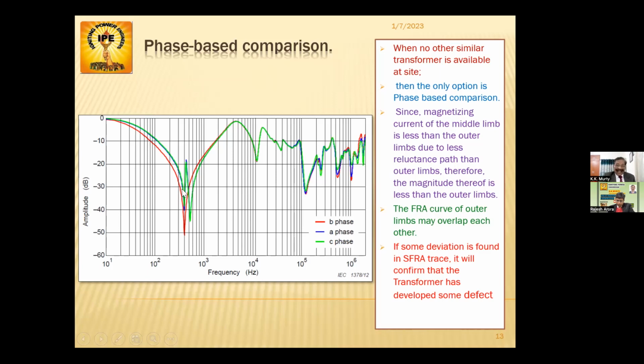So if some deviation is found in the SFRA trace, it will confirm that the transformer has developed some defect. What I have said is, the magnetizing current of the middle limb is less than the outer limbs, due to a shorter reluctance path. Therefore, the magnitude is less than the other limbs. Those who have worked in the field will see that while conducting the magnetizing current test, the current taken by the middle limb is less than the outer limbs.